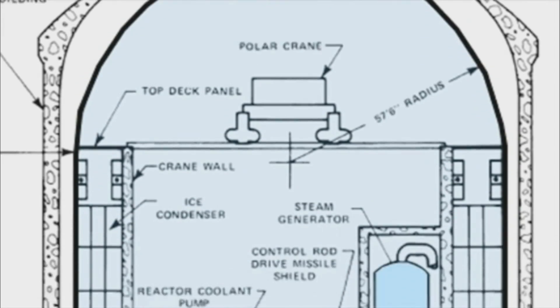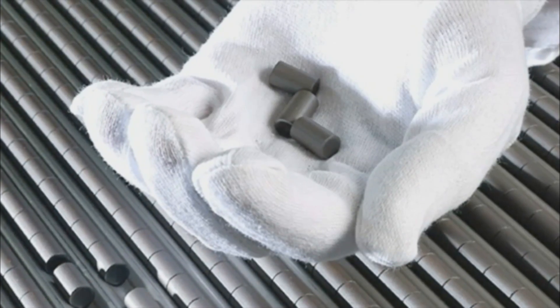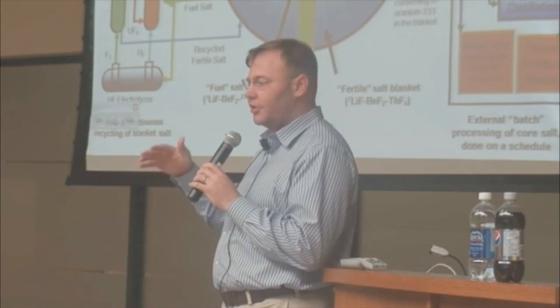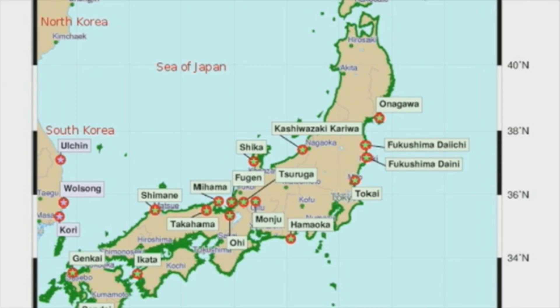This is what drives the design of this building. So if this happens, all the steam is captured in this building. Now the reactors we have today use uranium oxide as a fuel. It's a ceramic material — chemically stable, but not very good at transferring heat. If you lose pressure, you lose your water, and soon your fuel will melt down and release the radioactive fission products within it. So they have a series of emergency systems designed to always keep the core covered with water. We saw the failure of this at Fukushima Daiichi.